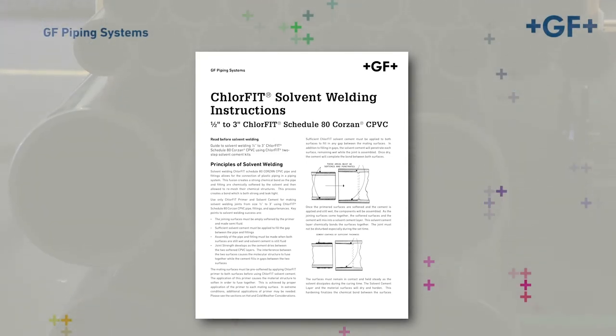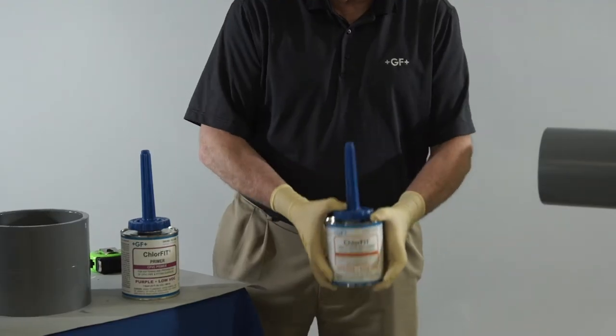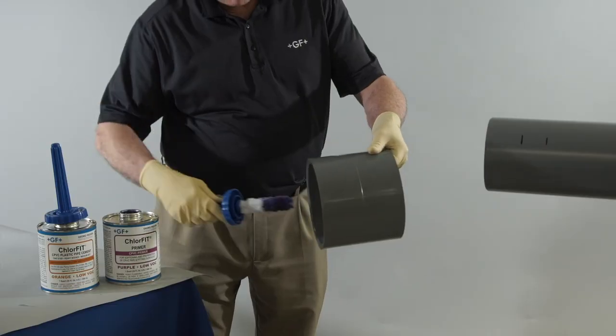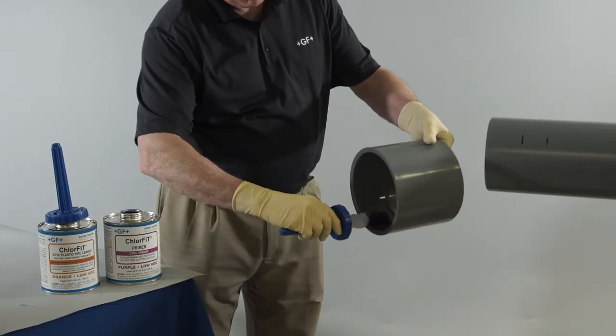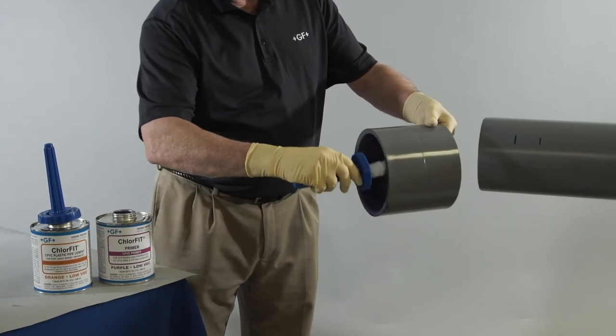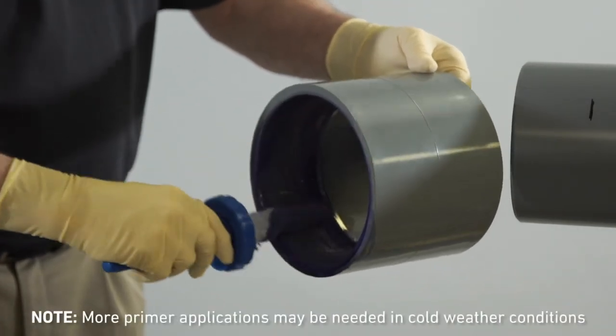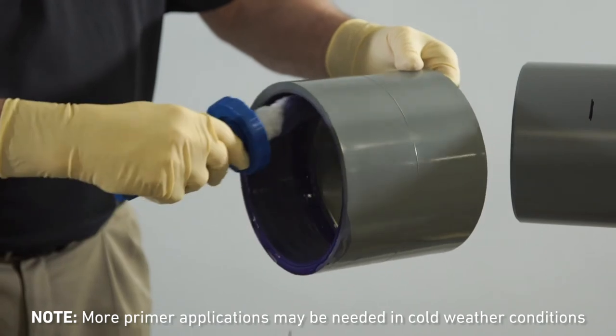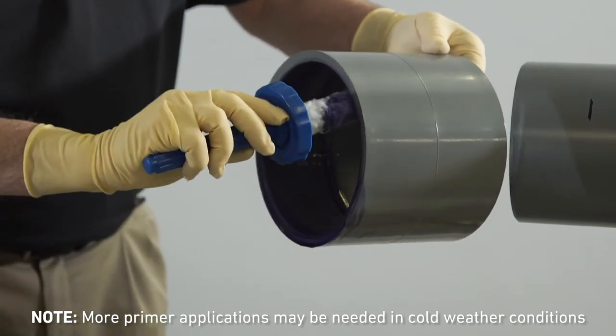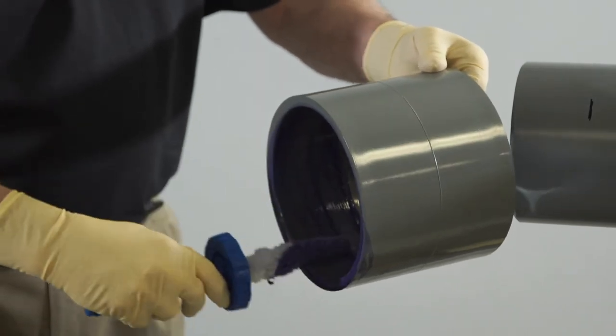To begin the solvent cementing process, ensure you have the correct applicators. The applicators should be approximately half the diameter of the pipe being solvent welded. Stir or shake the solvent cement before using. Aggressively apply the primer into the fitting socket, keeping the surface and applicator wet until the surface has been softened. While using the applicator inside the fitting socket, ensure the applicator remains in constant contact with the fitting socket surface. Redip the applicator in primer as required. More applications of primer may be needed in cold weather conditions.